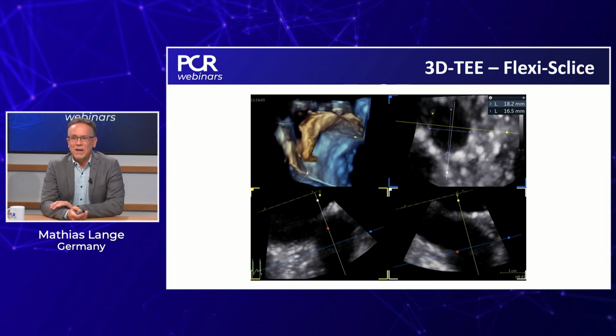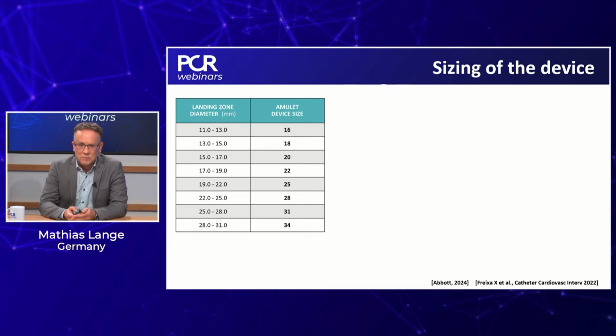What we did in our patient is a 3D TOE with flexi-slice, and we had a maximum diameter of 18.2 millimeters in the landing zone. And as you can all see, it's more a circular-shaped left atrial appendage landing zone rather than an elliptical one. So looking at this sizing chart for Amulet devices, you end up with a 22 millimeter device, probably a 25 if you go for a little oversizing because it's a circular landing zone.